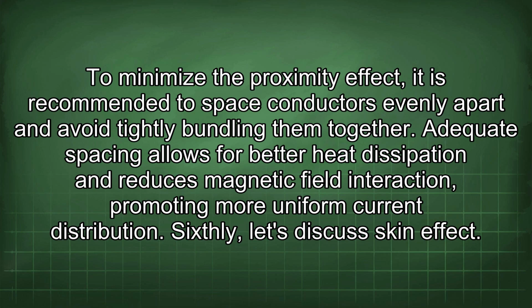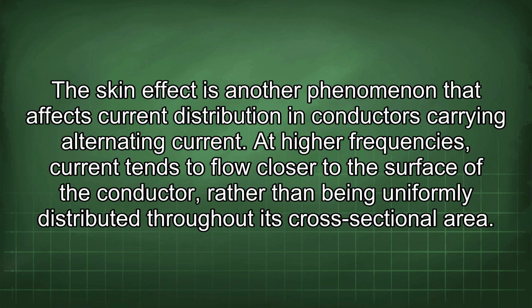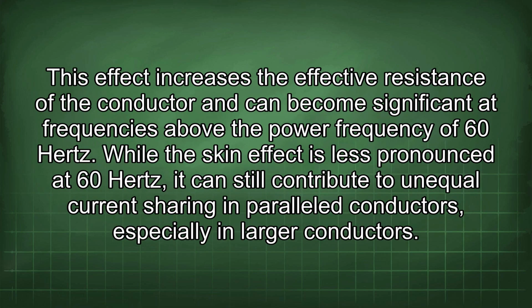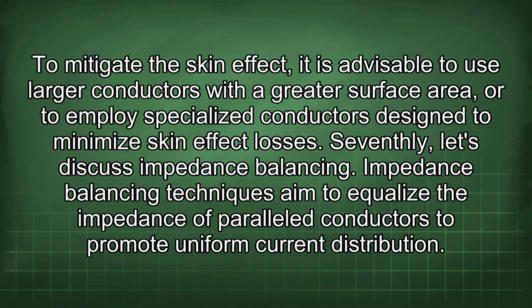Sixthly, let's discuss skin effect. The skin effect is another phenomenon that affects current distribution in conductors carrying alternating current. At higher frequencies, current tends to flow closer to the surface of the conductor, rather than being uniformly distributed throughout its cross-sectional area. This effect increases the effective resistance of the conductor and can become significant at frequencies above the power frequency of 60 Hz. While the skin effect is less pronounced at 60 Hz, it can still contribute to unequal current sharing in parallel conductors, especially in larger conductors. To mitigate the skin effect, it is advisable to use larger conductors with a greater surface area or to employ specialized conductors designed to minimize skin effect losses.